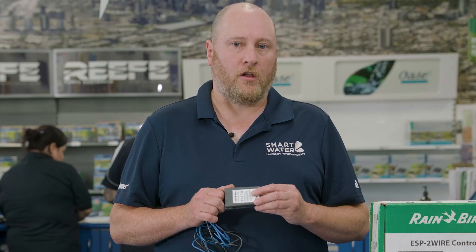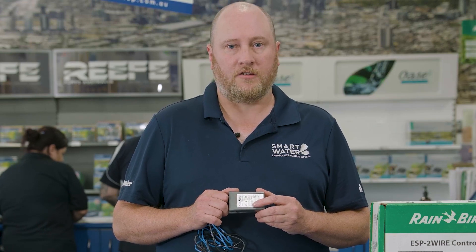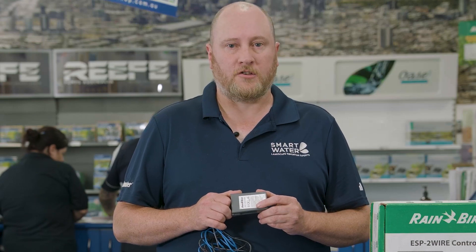decoder systems allow for longer runs of cable. The Rainbird ESP decoder system can be used with traditional two-core irrigation wire and the maximum run length is determined by the gauge of wire. As an example, with the two and a half millimetre cable you can run up to 790 metres to a single valve.